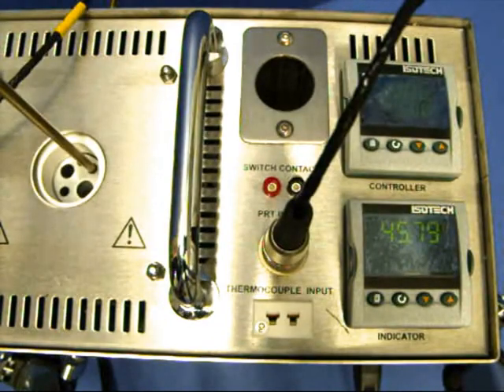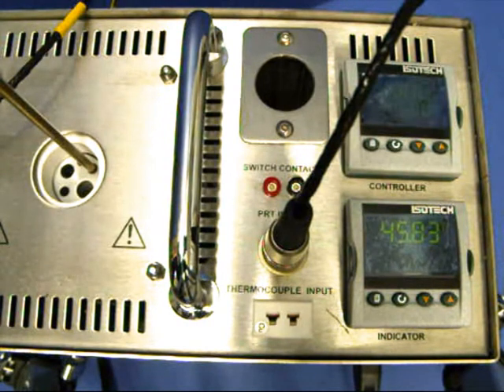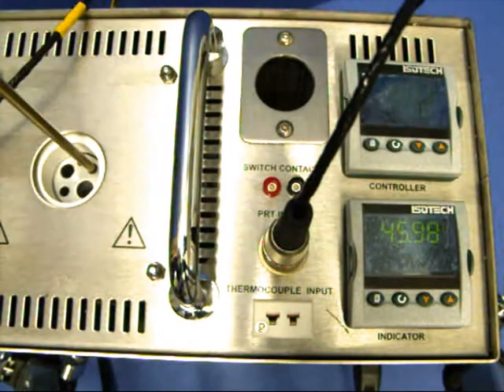Advanced indicator operation. The indicator can be configured with up to five custom calibration points. The points contain data pairs. First, the temperature point and second, the error offset at that point. Isotech dry block calibration certificates will show the values to suit a particular sensor. These values can be inspected and modified with the following procedure.